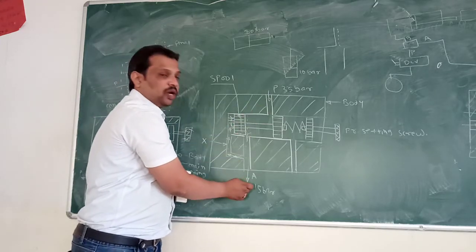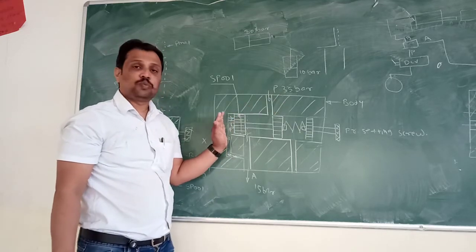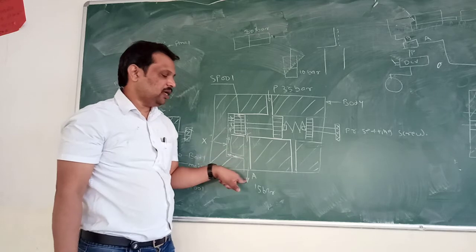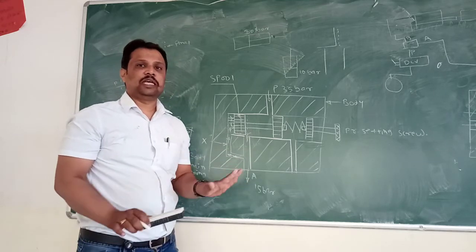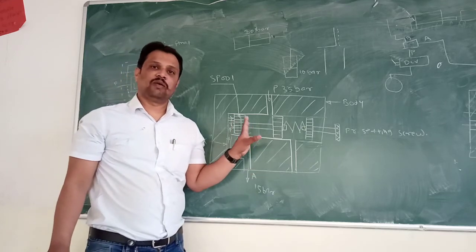And due to this blockage, your excess pressure is also blocked here and again you are getting the same pressure. If pressure rises, this spool will move towards the right and again your output pressure will be the same. There is no change in your output pressure. This is how pressure reducing valve works.